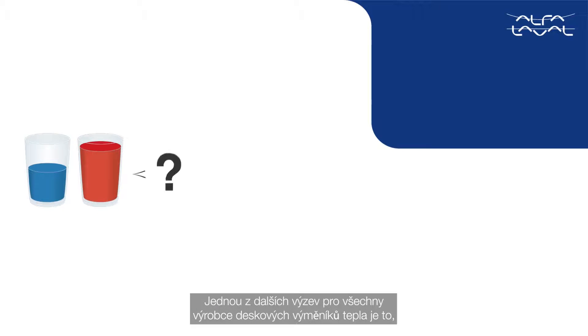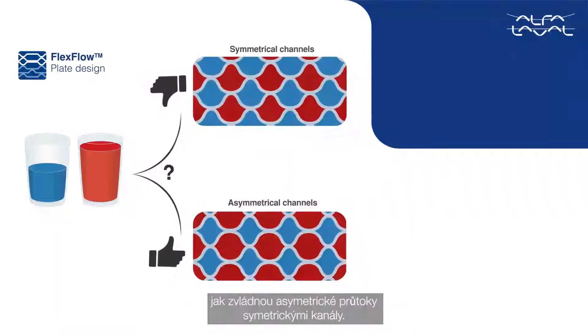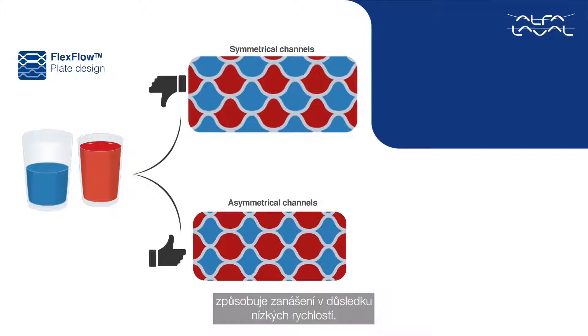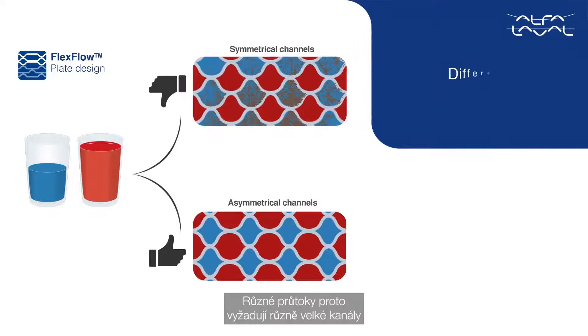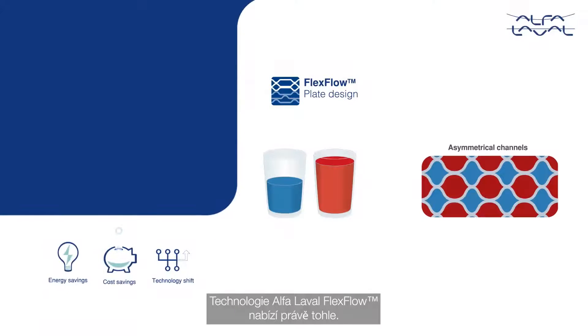One of the other challenges for all plate heat exchanger manufacturers is how to manage asymmetrical flow rates with symmetrical channels. The problem is that the lower flow rate fluid will start fouling due to lower velocities. Hence, different flow rates deserve different sized channels to minimize the likely fouling of the lower flow rate. Alfa Laval FlexFlow technology provides exactly that.